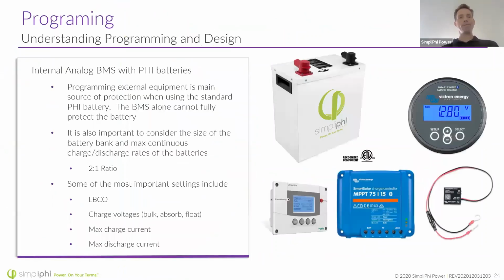So programming - if you're using a battery without communications, it is very important to program system equipment properly. What this means is that you have to pay attention to the capabilities of the battery. For example, the BMS system is really just there as a fail-safe. There is a breaker installed on every one of our SimpliPhi batteries, and that breaker can be tripped if too much current is there.